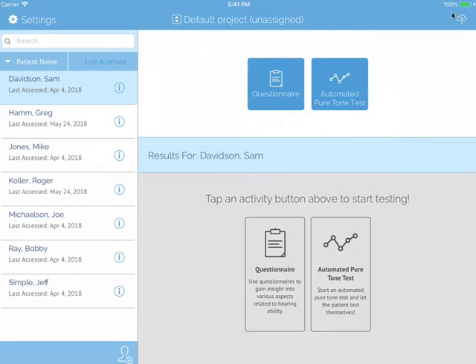When you are connected to Wi-Fi, anything that you create on the iPad — whether that be patients, projects, audiograms, or questionnaires — will automatically be copied over to the Shoebox Data Management cloud-based portal. You do not need to be connected to Wi-Fi to perform a test. In cases where you do not have Wi-Fi connection, the data will remain stored locally on the iPad. Once you have re-established your Wi-Fi connection, then the sync to the portal will take place.